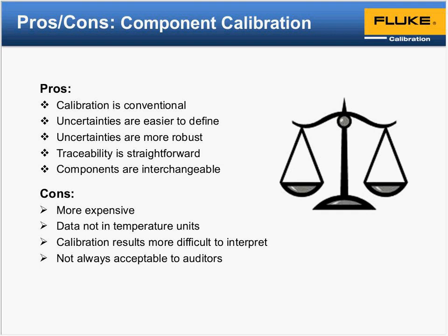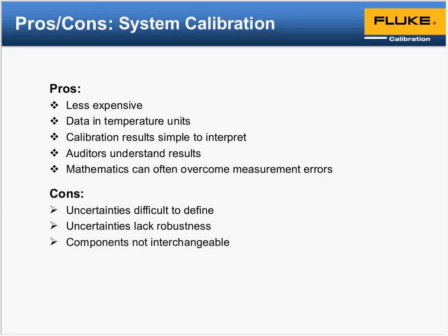Related to calibrating thermocouples, there's a question about the reference junction. Maybe you could talk a little bit about calibrating thermocouples and the reference. It's a little tougher to talk to because we don't have a whole lot of experience, since in our lab we typically only deal with the R and S thermocouples. Regarding the reference junction, to my understanding, when reading a thermocouple, there's what they refer to as an internal reference junction. If you have a readout and the internal reference, or CJC, is set to internal, it means as part of the measurement there's a temperature measurement that compensates for the temperature it's actually seeing.